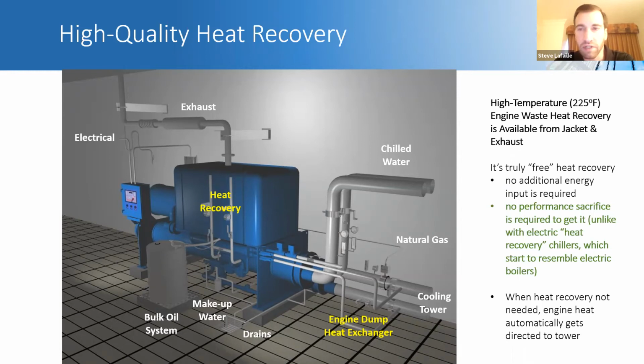Whenever the customer can use that heat, that's the first place we're going to send it. Then, through a series of thermostatic valves, if it starts coming back to the machine too warm, meaning they're not using it, we typically automatically reject it to the cooling tower through this dump heat exchanger and these other connections. That's 99% of the case.